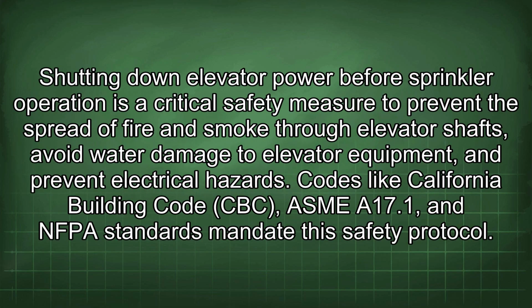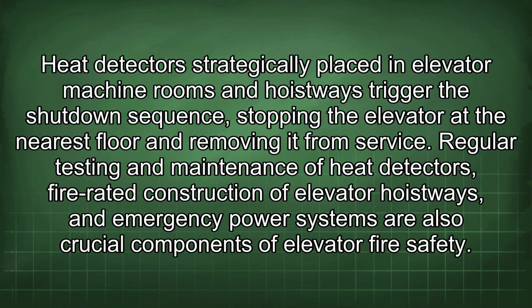Shutting down elevator power before sprinkler operation is a critical safety measure to prevent the spread of fire and smoke through elevator shafts, avoid water damage to elevator equipment, and prevent electrical hazards. Codes like California Building Code CBC, ASME A17.1, and NFPA standards mandate this safety protocol. Heat detectors strategically placed in elevator machine rooms and hoistways trigger the shutdown sequence, stopping the elevator at the nearest floor and removing it from service.